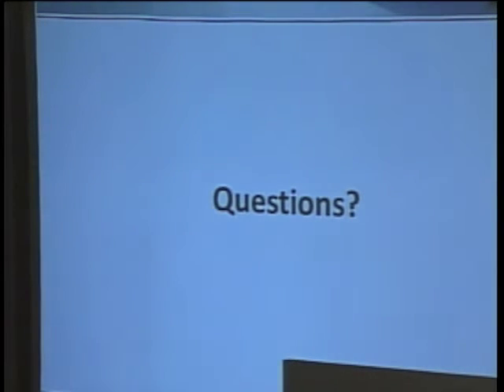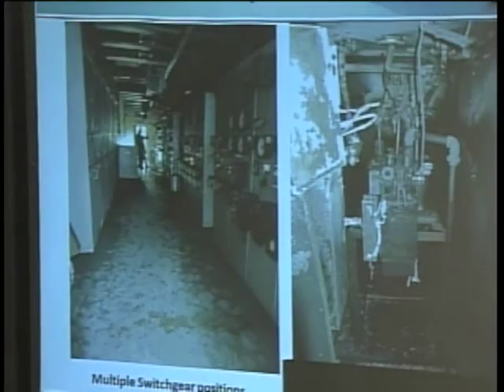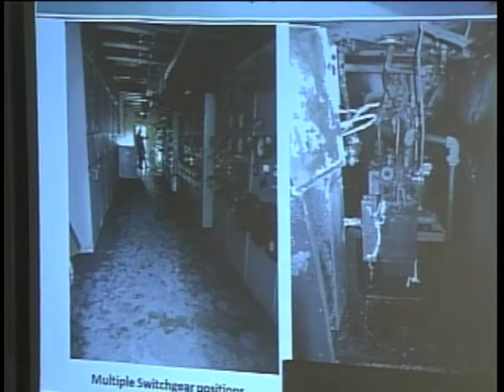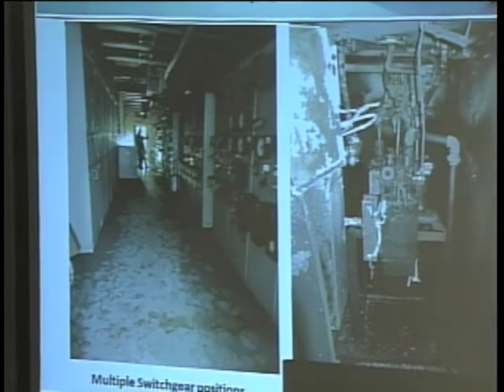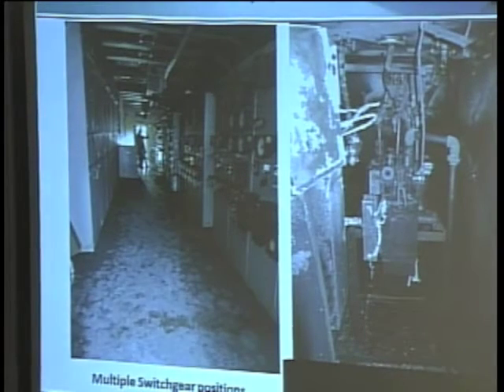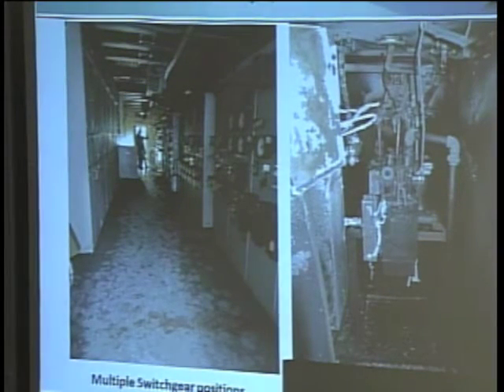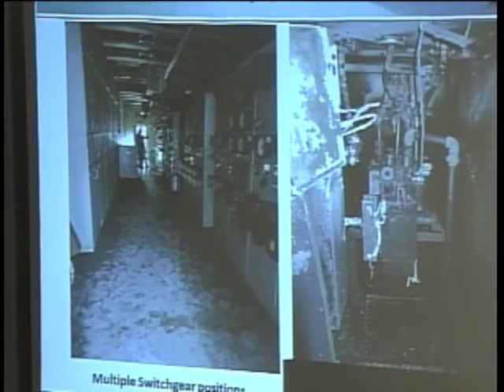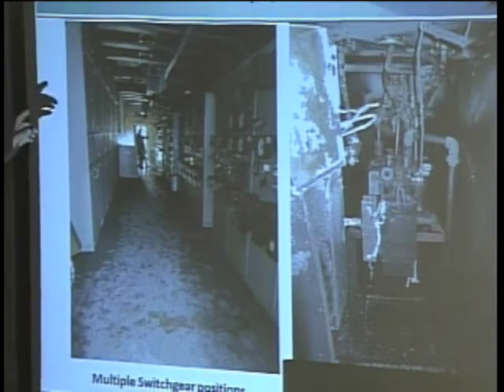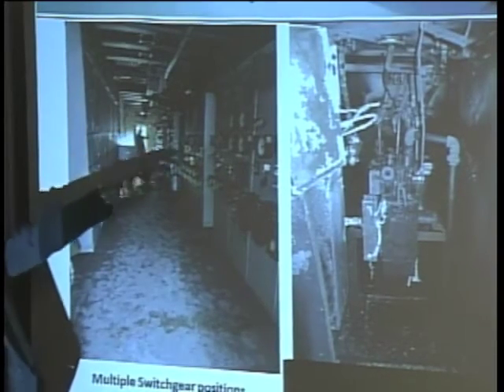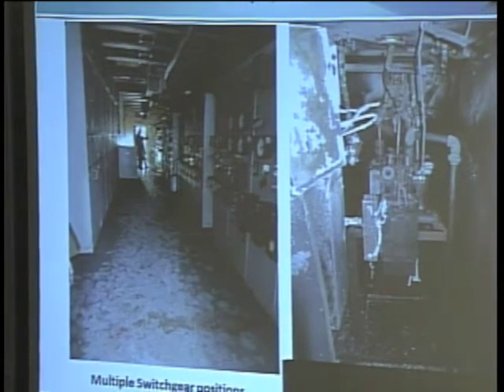And that's questions, but I do have one more slide. I just thought it'd be interesting to see what the substation looks like inside during the fire. The column on the left indicates the main aisleway of the substation. We've got metal clad switchgear, and what that means is that each of these compartments with the handles is a position where there's a circuit breaker inside. The breaker would be in this column, and then there are conduits across over to the relaying and controls and meters that indicate how much load you have on the circuits.